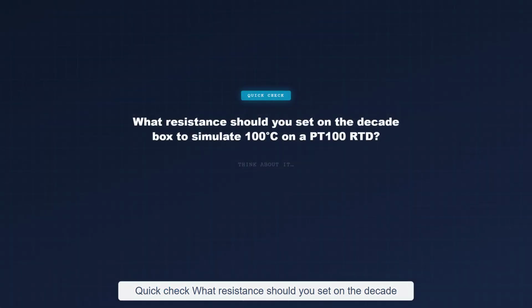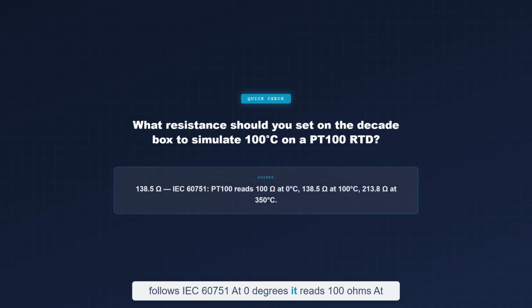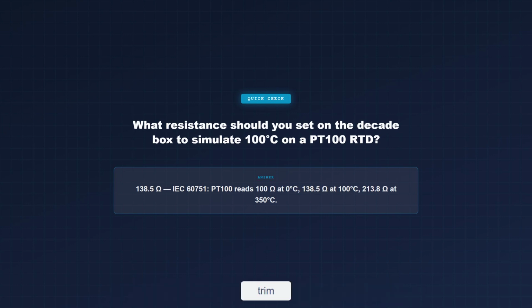Quick check. What resistance should you set on the decade box to simulate 100 degrees Celsius on a PT100 RTD? Think about it. The answer is 138.5 ohms. A PT100 RTD follows IEC 60751. At 0 degrees, it reads 100 ohms. At 100 degrees, it reads 138.5 ohms. At 350 degrees, it reads 213.8 ohms. These are the values you dial in during sensor trim.